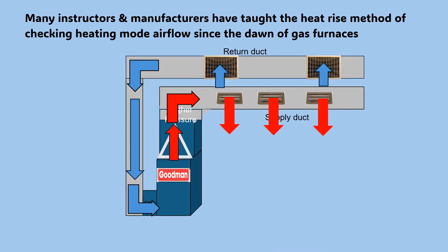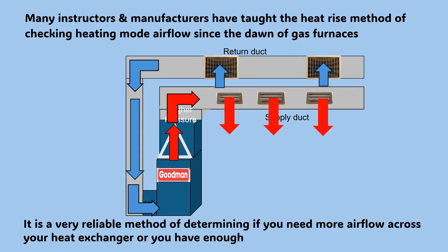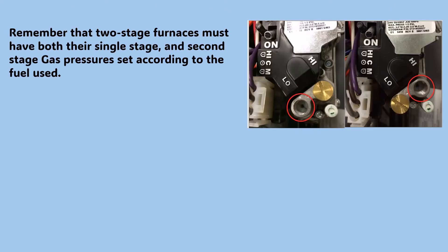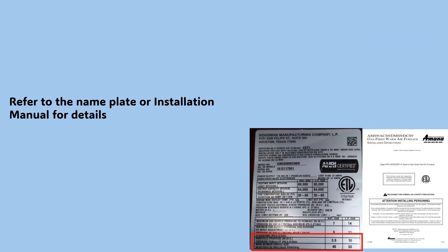Many instructors and manufacturers have taught the heat rise method of checking heating mode airflow since the dawn of gas furnaces. It is a very reliable method of determining if you need more airflow across your heat exchanger or you have enough. Your filter must be clean and your gas pressure set correctly. Remember, the two-stage furnace must have both its single-stage and second-stage gas pressures set according to the fuel used. Refer to the nameplate or installation manual for details.